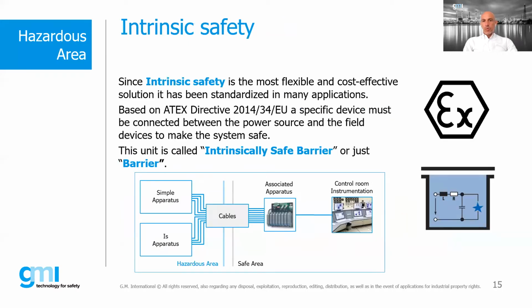And so intrinsic safety is very interesting because it's the most flexible and cost-effective solution, because it's realized by electronic circuits that prevent sparking in the hazardous areas. Between the hazardous area and the system side, you can use this kind of interface, which is called an intrinsically safe barrier, or just barrier. The unit is installed in the safe area, or even in zone 2 if the certification is available for that area.